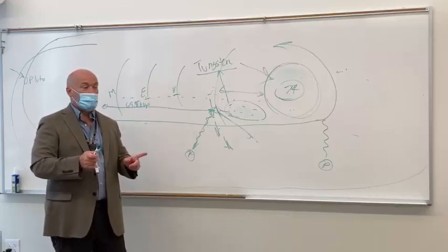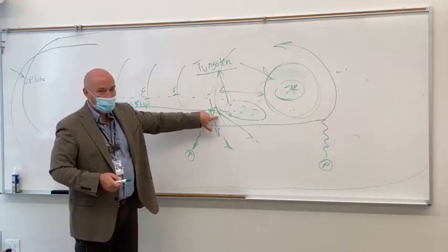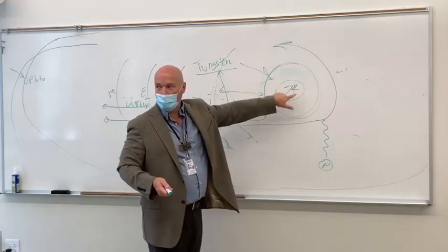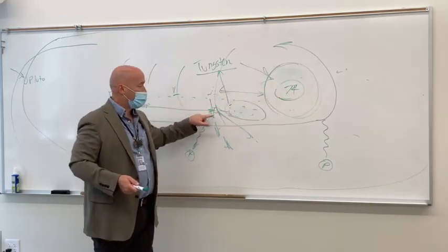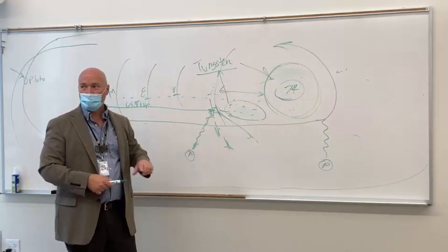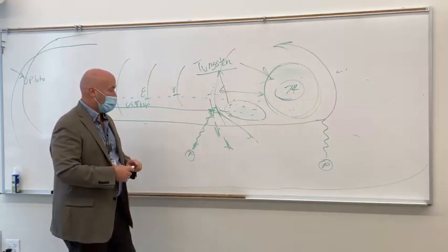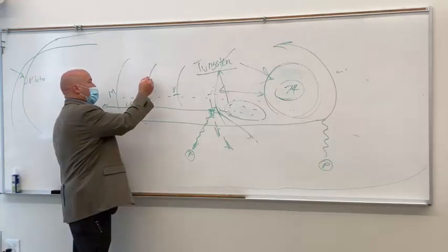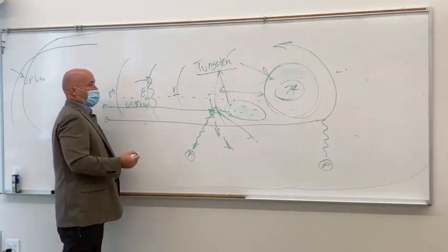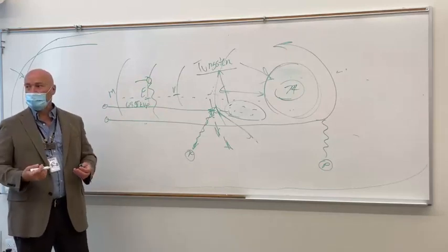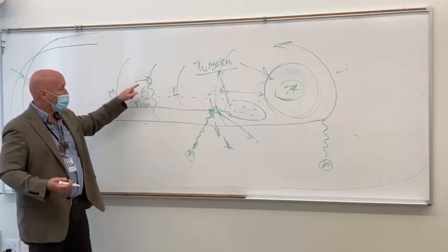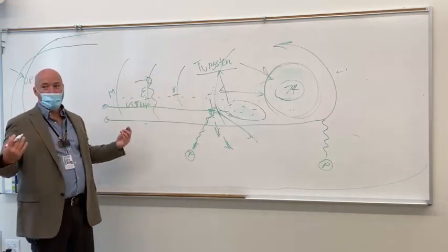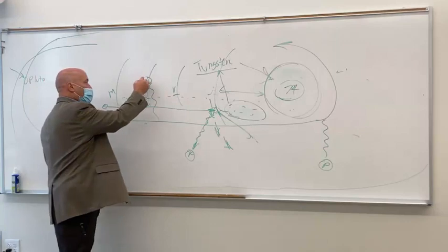It's not changing the characteristic of the tungsten atom, it's because that binding energy is characteristic of the tungsten atom. If we change the atom, we change the binding energy, we change the energy of the characteristic photon. Characteristic photons, we're going to see them all over the scale. If we ejected this one, we're going to create an X-ray photon, it's just going to be so low energy we don't care about it. But it's still characteristic of the tungsten atom, because that binding energy is characteristic of the tungsten atom, right? But we don't care about it, so we're not going to recognize it.